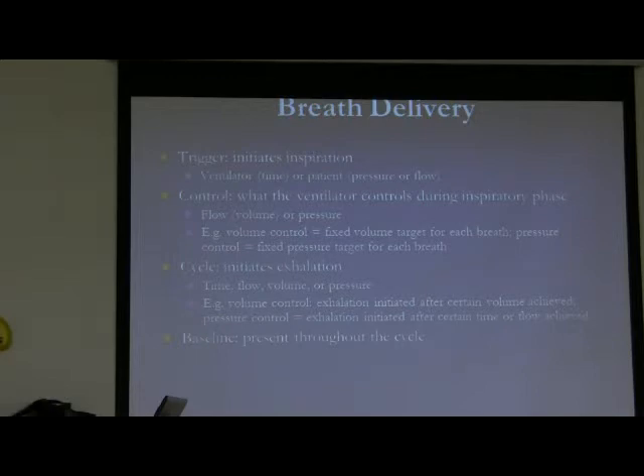All right. Then there's another thing that's present all the time. It doesn't matter if the breath is triggered, or it's inspiratory time, inspiratory breath, or an exhalation phase of the breath. It's there all the time, and that's PEEP. Okay, so that's positive end expiratory pressure. That means at the end of the breath, you still have an amount of positive pressure that's inside, that you're actually giving the patient. It's externally applied.